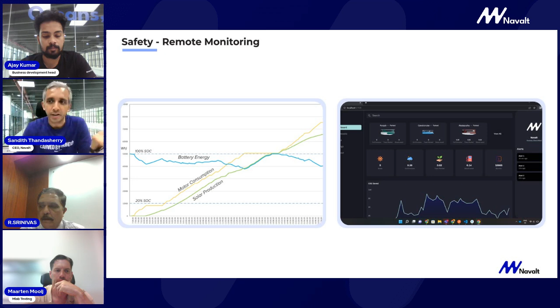We also have all our batteries typically fitted with remote monitoring, including cell-level monitoring, to monitor on an online basis and also perform certain analysis. This helps make the quarterly inspection merely a simple physical check, since the rest is done online. So remote monitoring is again a very important part of battery safety.